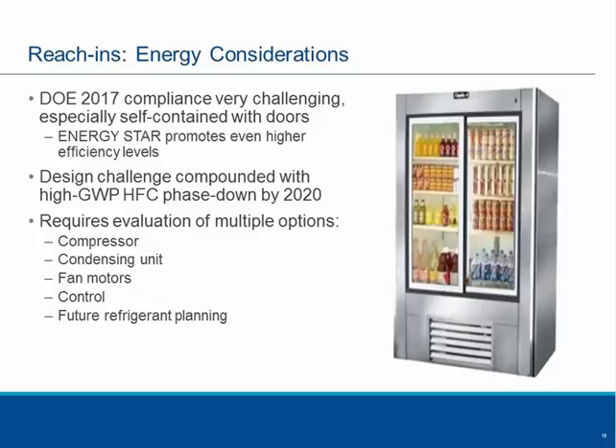levels. Now, Ani talked about the phase down of certain high GWP refrigerants, and for self-contained reach-in equipment, 404A and R134A are two very common HFC refrigerants used today. By 2020, those will be phased out for these applications, and equipment manufacturers will have to look at options. We mentioned R290 propane as a possible refrigerant for some of these applications. It's not perfect. It's a good refrigerant, but it's not perfect for every application.